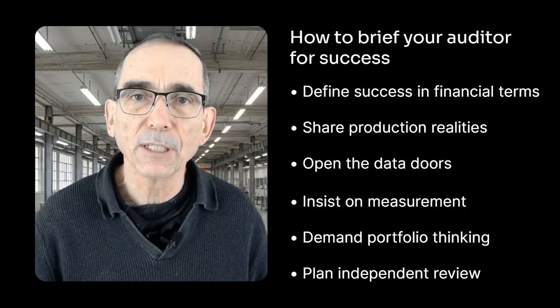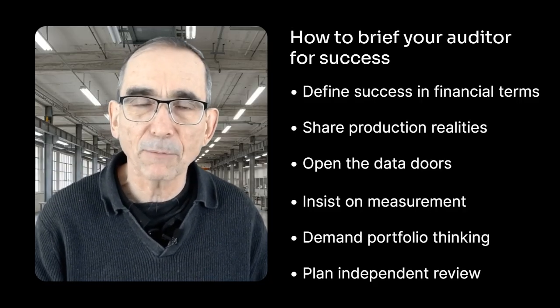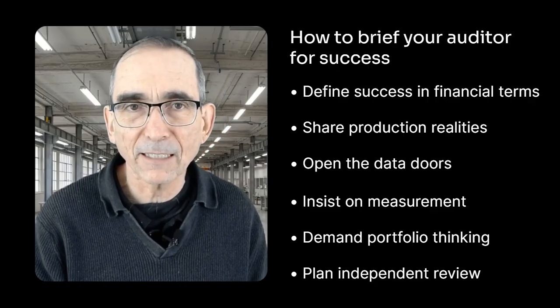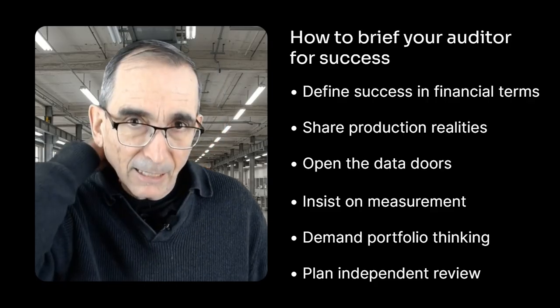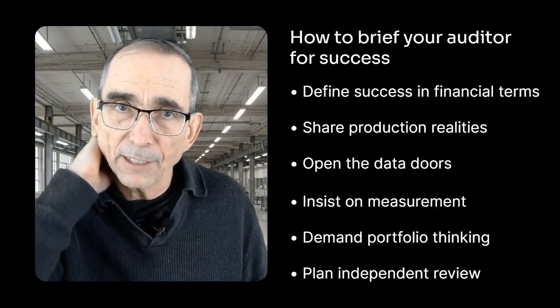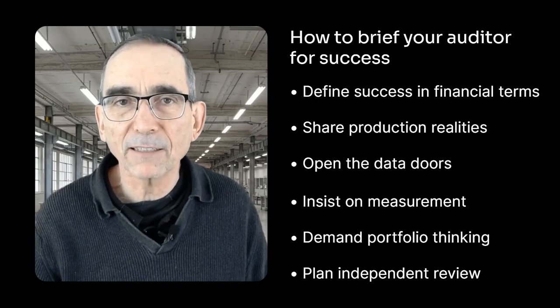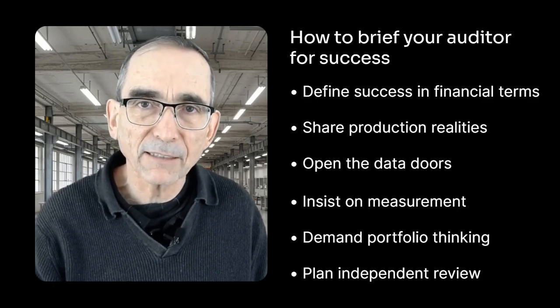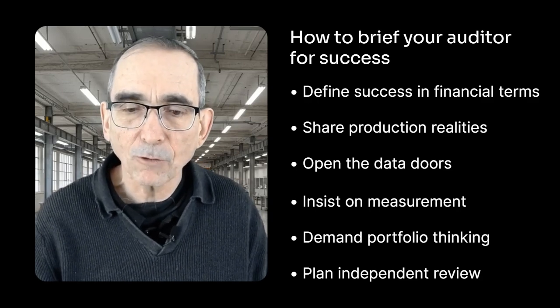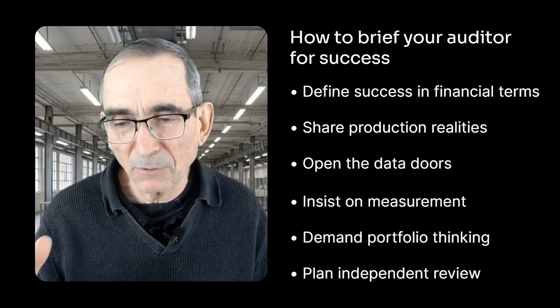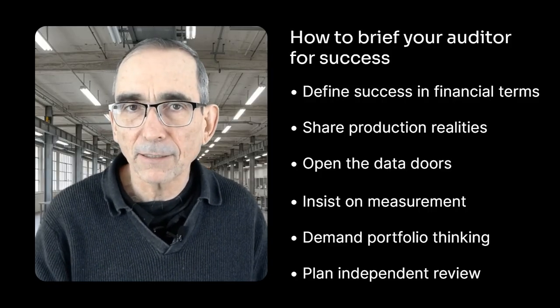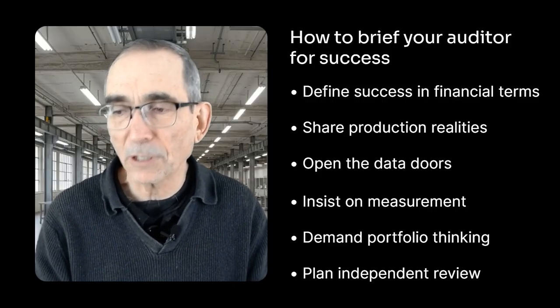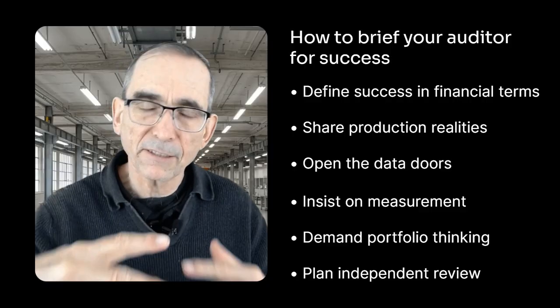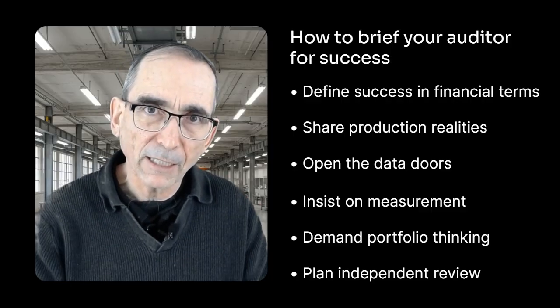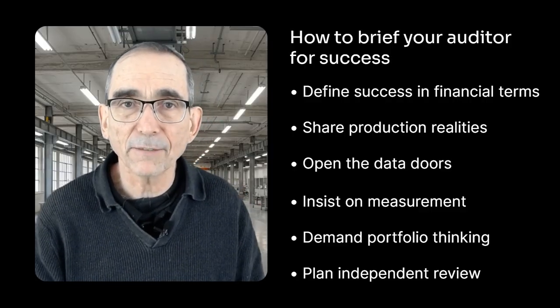And consuming this data, you need to open the data door. Give them bills, give them interval data, give them SCADA trends, give them access to the SCADA system, give them the tag names for the different equipment used in the SCADA system, give them maintenance logs, show them data on rejects, give them ambient utility data. And ultimately, a good auditor is interested in the business improvement, not just the energy improvement. So things that you might think are a bit tangential could actually be really useful for an energy auditor. Start to think of system changes that may give some really valuable savings at the site.